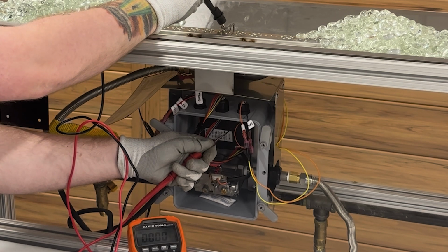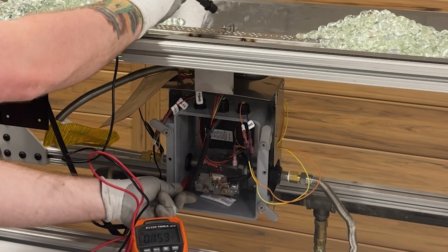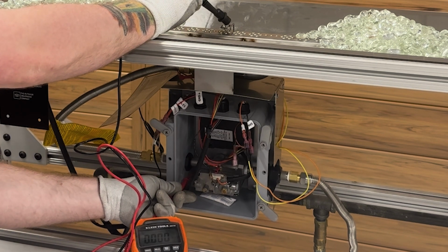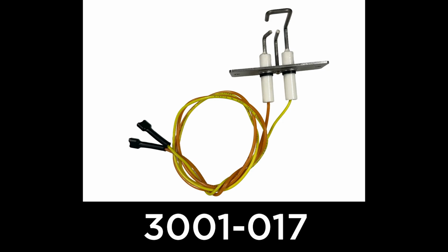Lastly, check for continuity of the sensor and ground circuit separately. To do this, disconnect the sensor wire from the module and connect one probe of your multimeter to the wire connector and the other to the actual sensor rod as shown here. Do the same thing with the ground circuit. Put one probe on the ground rod and simply touch the metal body of the valve with the other probe. If one of these circuits does not have continuity, you'll need to try to reclaim the rods or replace the entire electrode. Again, order part number 3001-017.